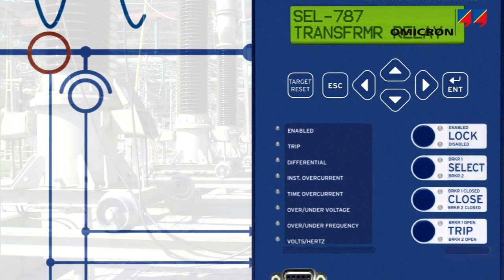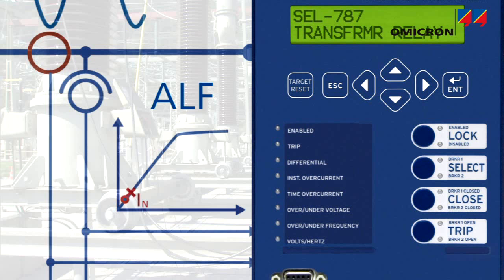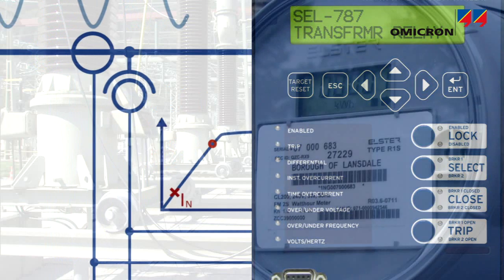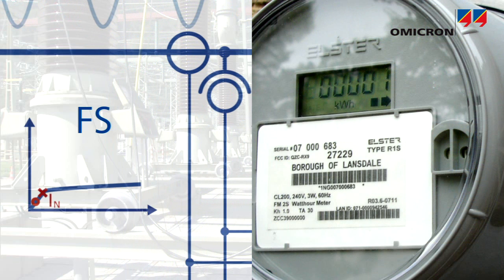Protection CTs must be capable of driving high-fault currents to the protection system without saturation. And vice versa, metering CTs must provide accuracy within the range of operational currents and saturate slightly above that range in order to protect the energy meters.